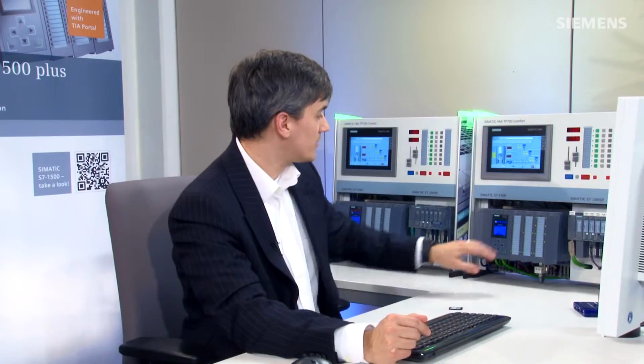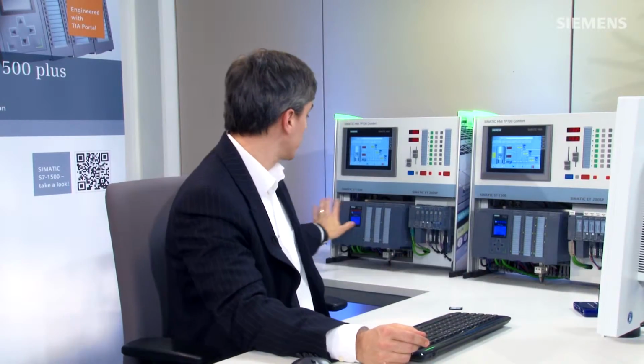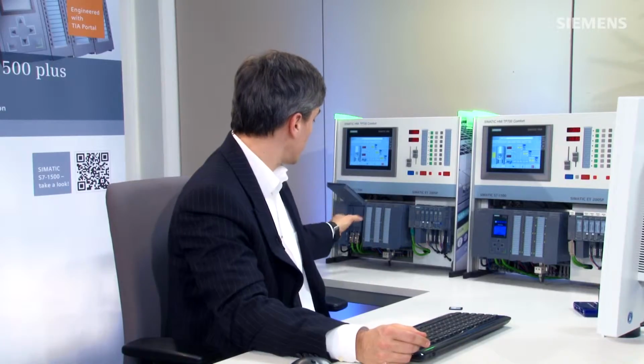As you can see here, I have the S7-1500 with some local I/O, an ET 200SP distributed, and a Comfort Panel, all of which is on Profinet. I've also got a memory card, which is required for the S7-1500, where I have the configuration and the code located. Right next to it I have the exact same configuration, however I have no memory card and I have no code. So what do I want to do? I want to protect this card from being copied.